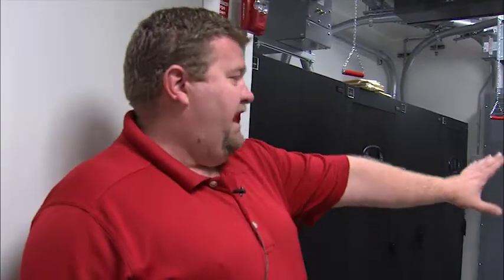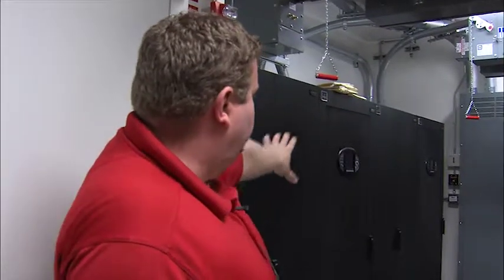We have battery cabinets for each system on both sides, and there's an internal bypass wraparound for each UPS. So if Liebert Services had to come and work on one UPS at a time, they can take just one down, put an internal bypass, and work on the unit itself, still having 3 tiers of redundancy for your load.